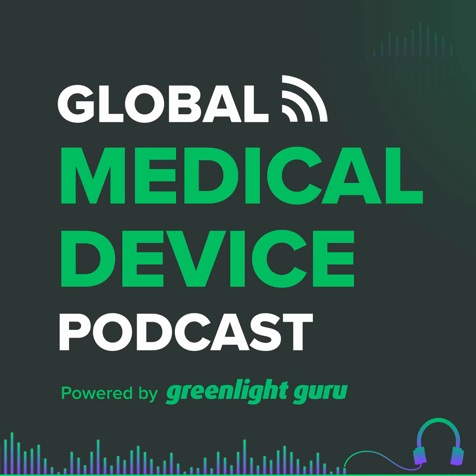And it's not yet available, at least for the general public, for PMA devices. I think Patrick could speak to where eSTAR will be going in the future. But for right now, everybody that's submitting a 510(k) needs to be using eSTAR. There's also a beta version for pre-subs right now that I think pretty cleverly they termed pre-star. I like that. Honestly, I think that one needs a bit of work, but look forward to that one evolving just like eSTAR has.